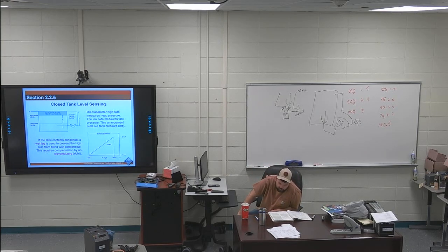The immediate next paragraph, the first three sentences are highlighted. However, if the gas in a closed pressurized vessel condenses, the condensation will eventually fill the low side piping or tubing. To address this issue, the low side tubing or piping is purposely filled with a convenient reference fluid. This filled pipe is known as the wet leg. Did I go with that? Moving on. They do more of the span calculations. I don't have any of those highlighted.